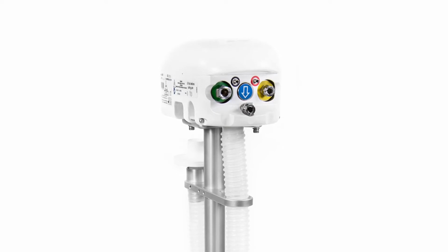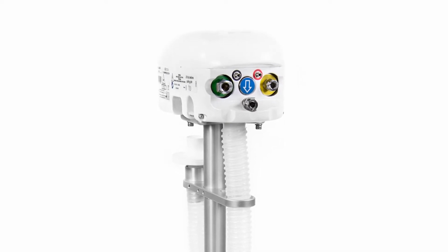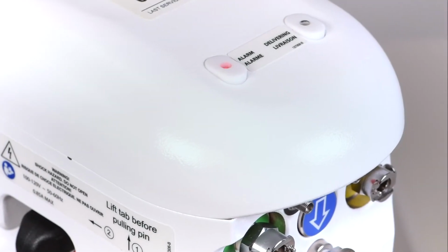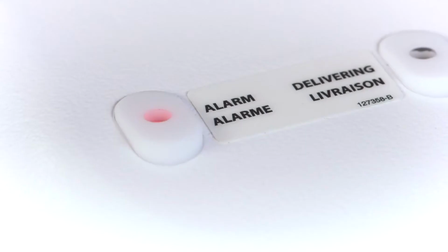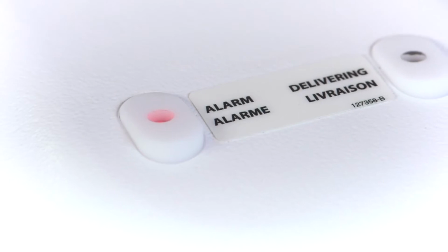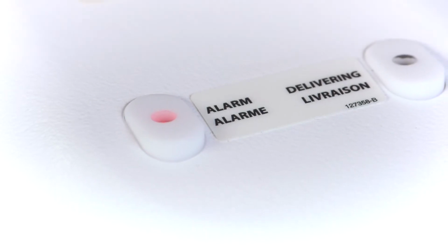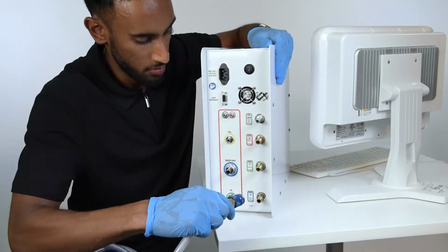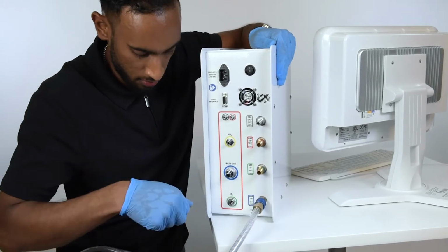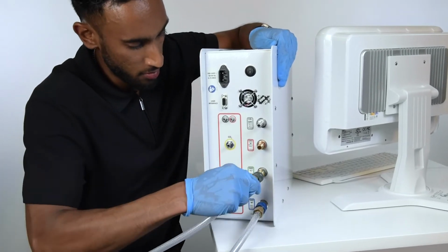Connect the RespirAct MRI unit to a power source, allowing the unit to warm up for 10 minutes on startup. You will notice that the alarm LED on the MRI unit blinks red. This can be disregarded since it is not connected to the rest of the system and does not have proper communication at this time.